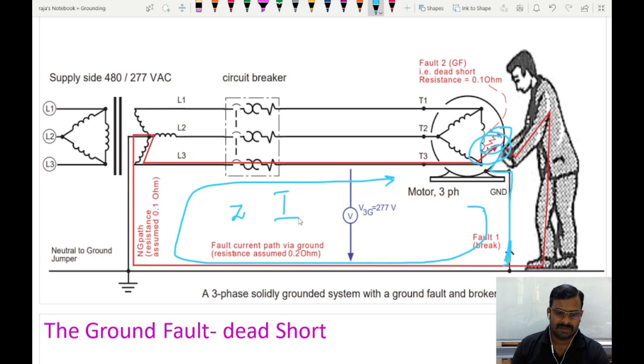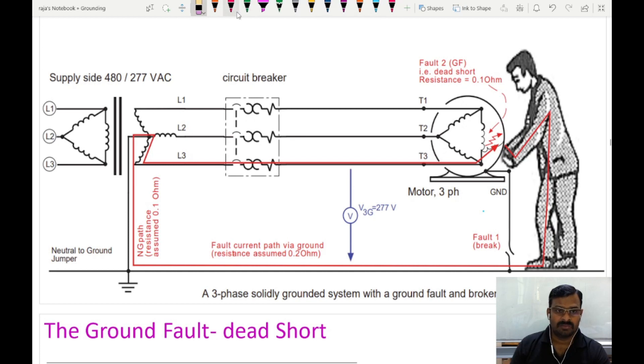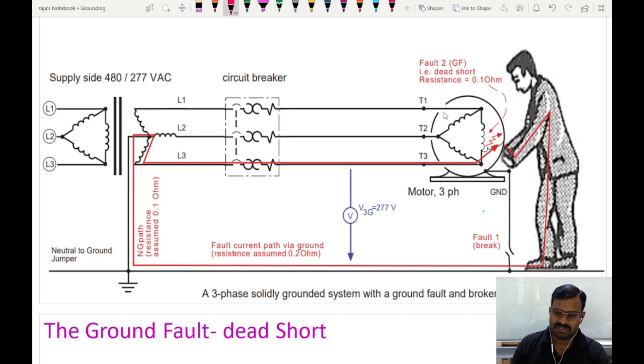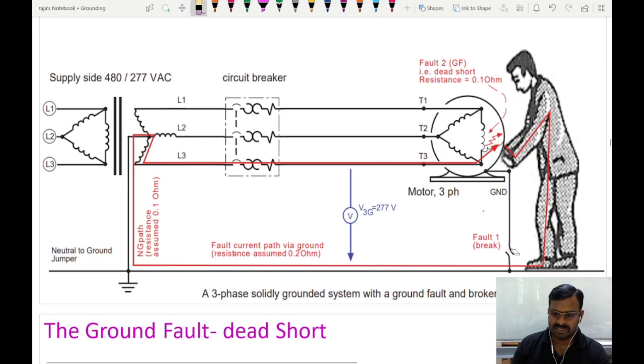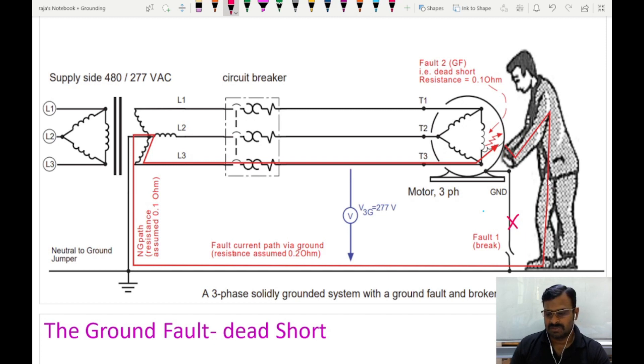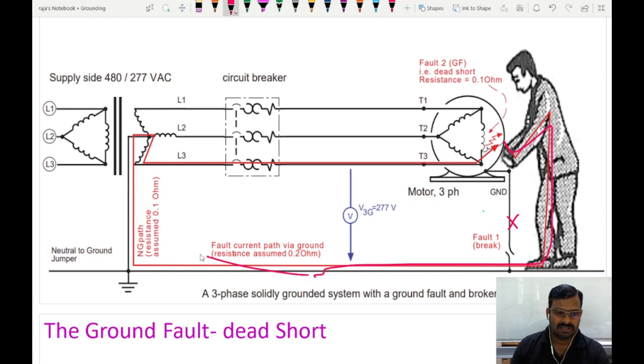Because the fault current will be very high, let us now consider the other case where the equipment ground conductor is broken. What happens during this condition? When the human comes in contact with this machine and if this conductor is not broken, the high current which is flowing will automatically trip the circuit breaker. But in case of breakage, no current will flow through that path. Instead, the electrical current flows through the human body and returns via a different path. Now the total resistance depends upon the resistance of the human body.